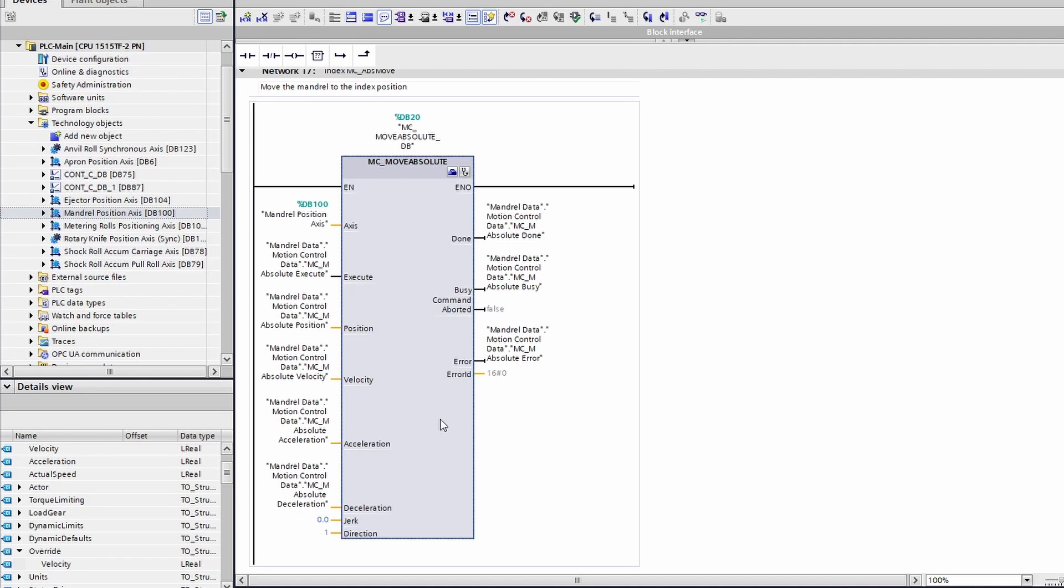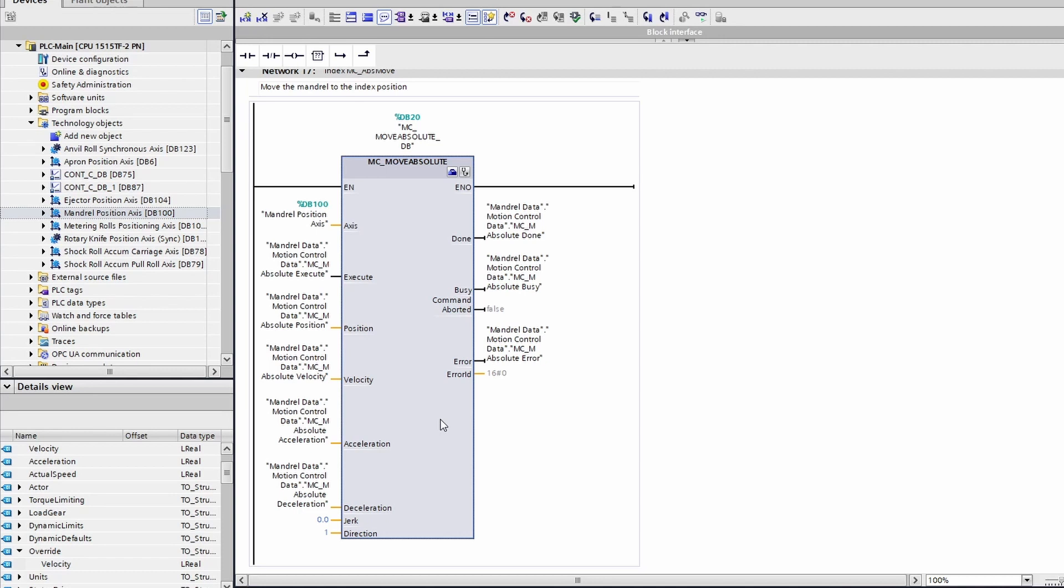If you are trying to execute 100 degrees of movement and you are sitting on zero, you can perform either a move absolute to position 100 degrees or a move relative with a position of 100 degrees. The difference is if you execute that same function afterwards, the move absolute will not move because it's already sitting on 100 degrees. The move relative will execute the move again and move another 100 degrees.